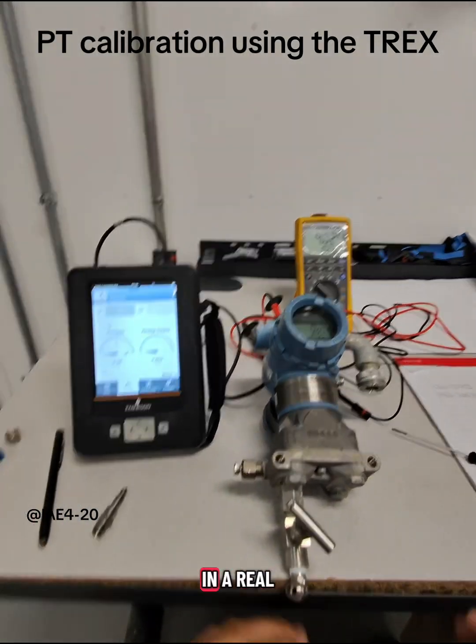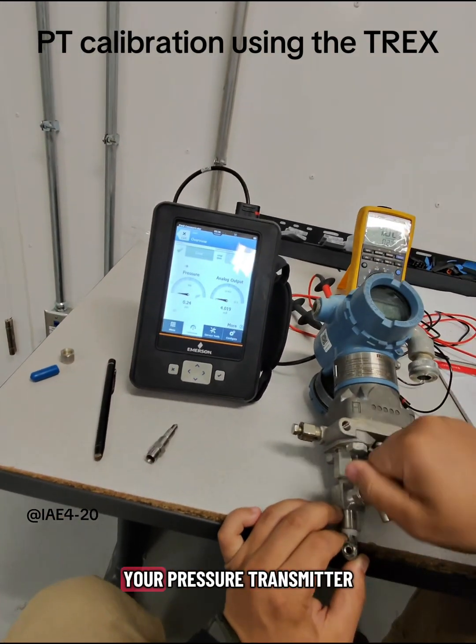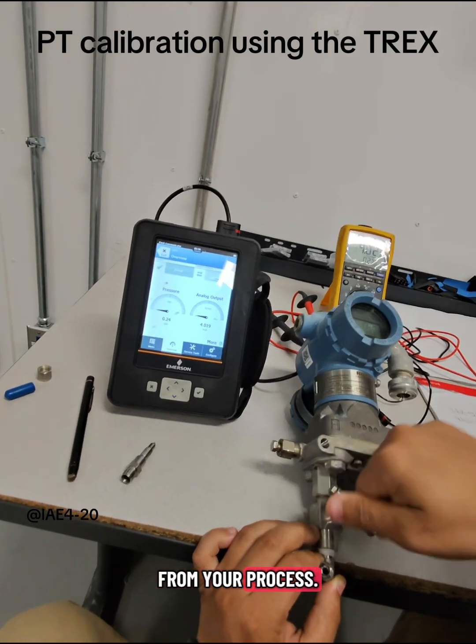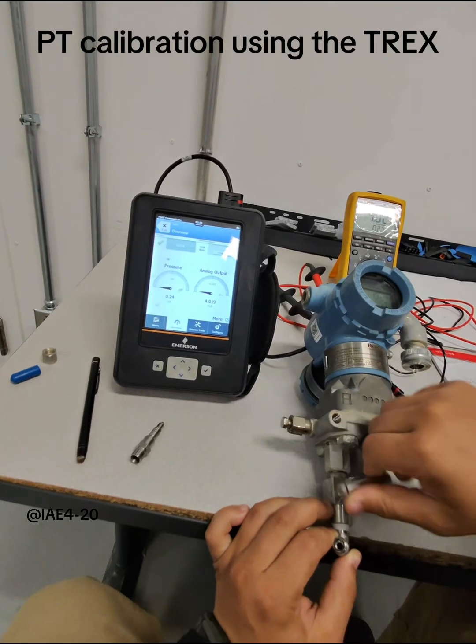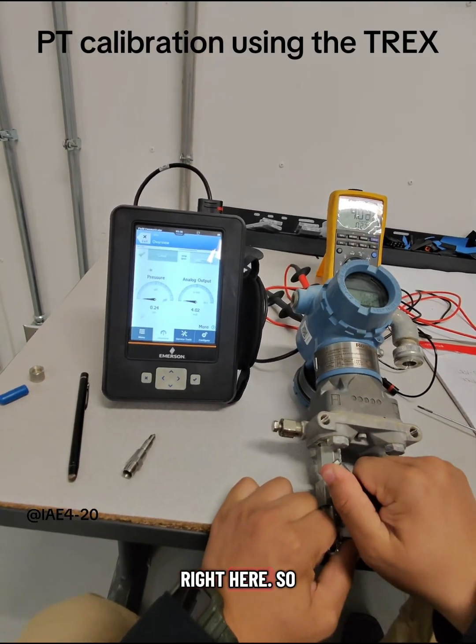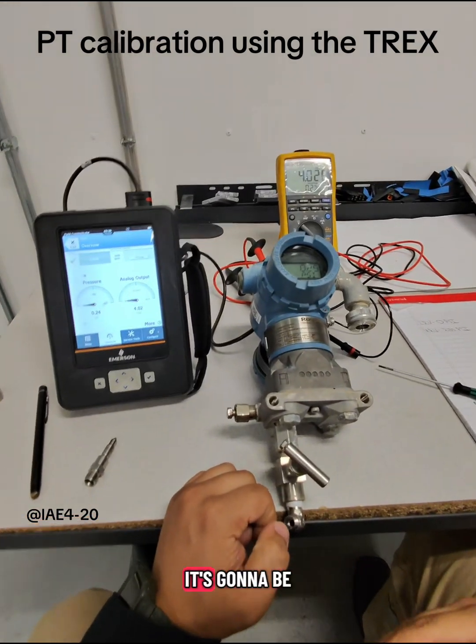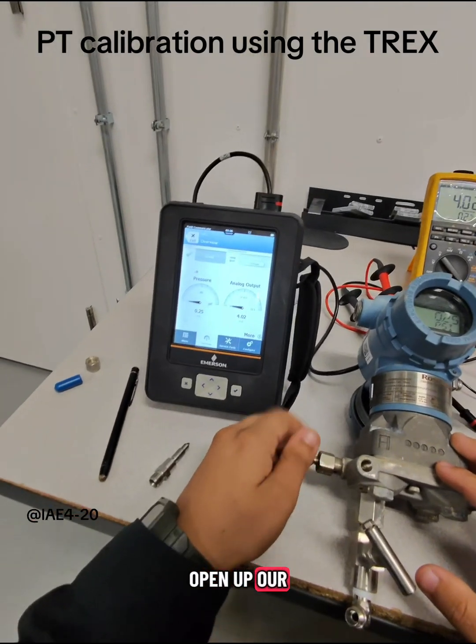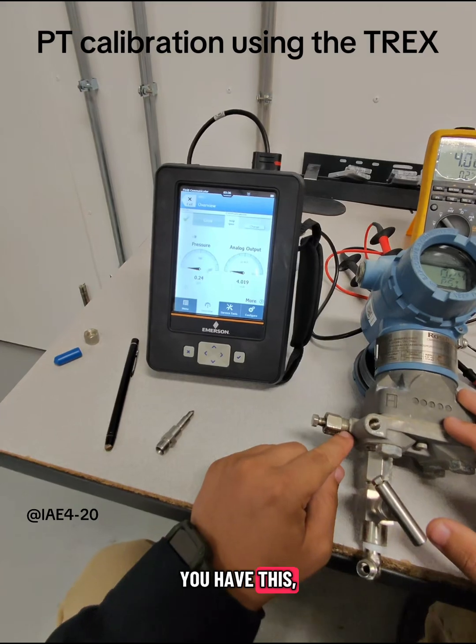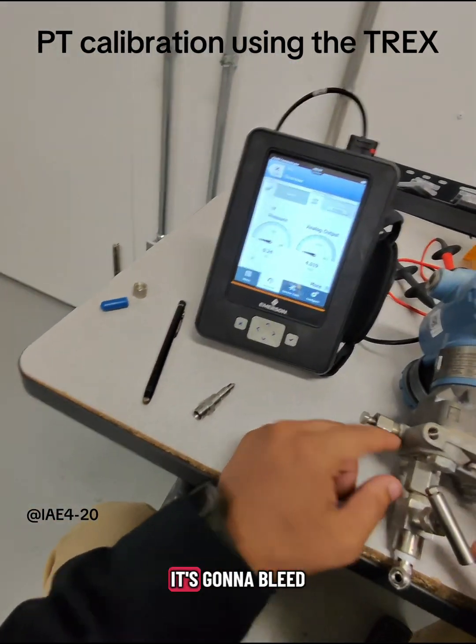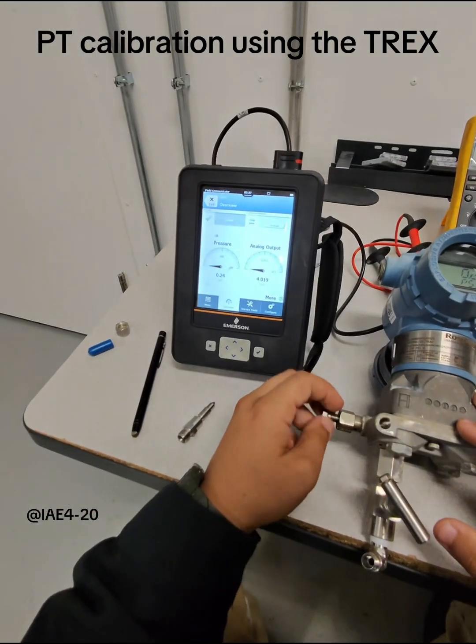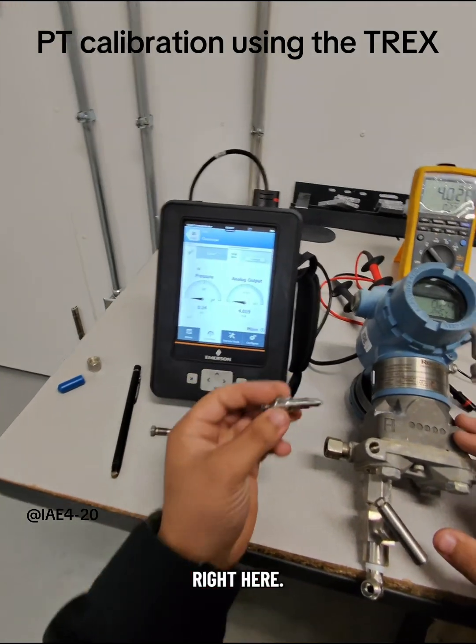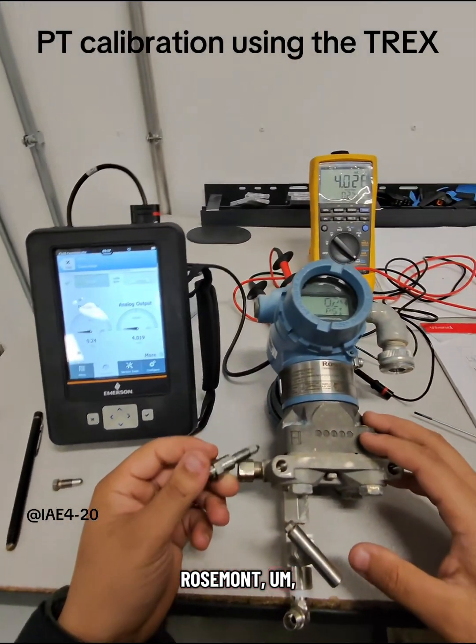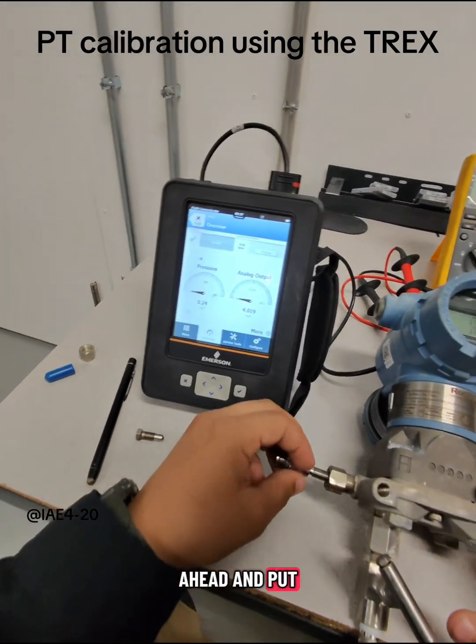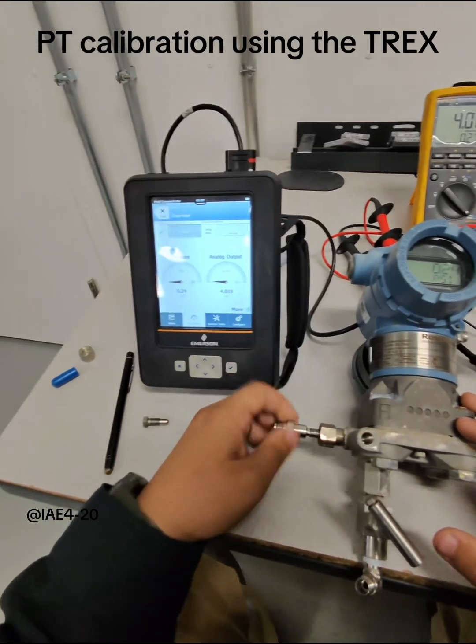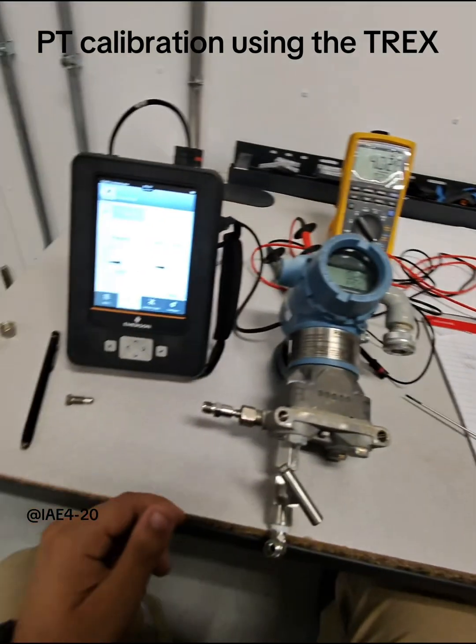First things first, in a real situation, you want to go ahead and isolate your pressure transmitter from your process. So you close this valve right here. So anything process-wise down here is going to be isolated. Then we'll go ahead and open up our bleeder. Right here you have this bleed port. It's going to bleed out any excess pressure. And then we have our stinger right here. This is for Rosemount pressure manifolds. Go ahead and put this in. That tightened up.